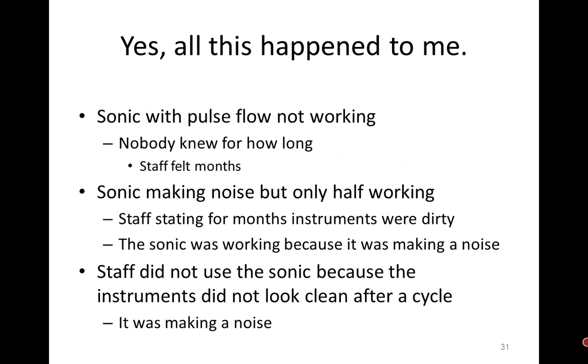I've also seen a sonic making noise, but only half of it was working. Staff said for months the instrument seemed dirty, like only half was getting clean. The sonic wasn't working, but they thought it was because it made a noise, even though they didn't have faith it was cleaning. Staff did not use the sonic because instruments did not look clean after a cycle. It was just making noise.